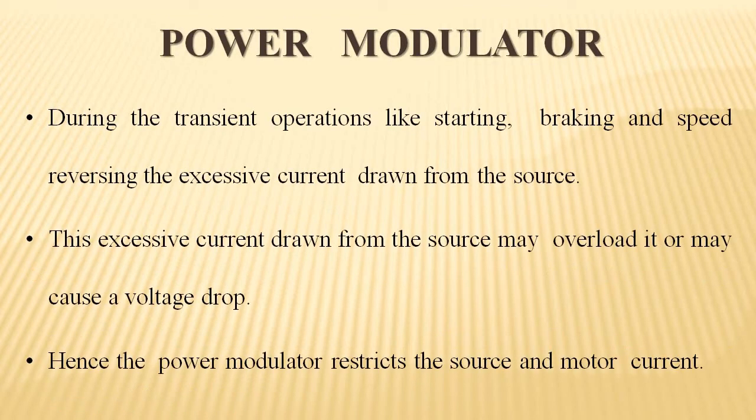During transient operations like starting, braking, and speed reversing, excessive current is drawn from the source. This excessive current may overload the source and cause a voltage drop. Hence, the power modulator restricts the source and motor current.